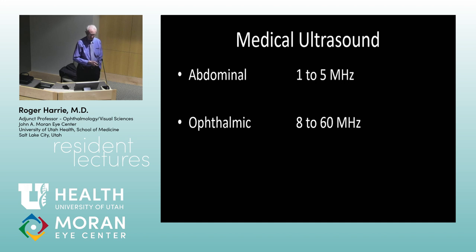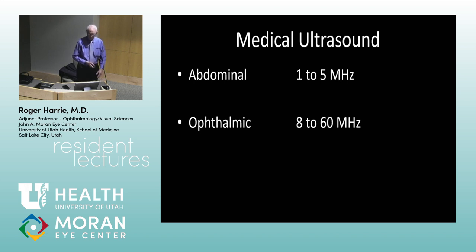In medical ultrasound, abdominal frequencies are lower because higher frequency means less penetration — there's an inverse correlation. In the abdomen you want to go deeper to see kidneys and livers, so you keep frequency around the 1 to 5 megahertz range. In ophthalmology we have the advantage of a small structure — about an inch — with a lot of fluid, so ultrasound goes through easily. You can use high frequencies up to 60 megahertz, giving much better resolution.